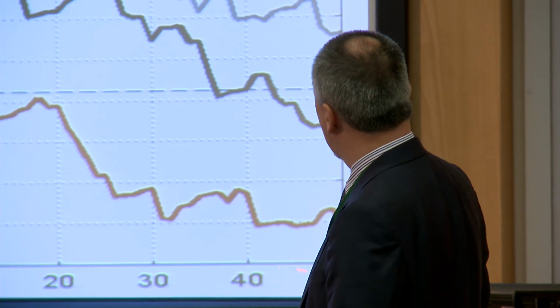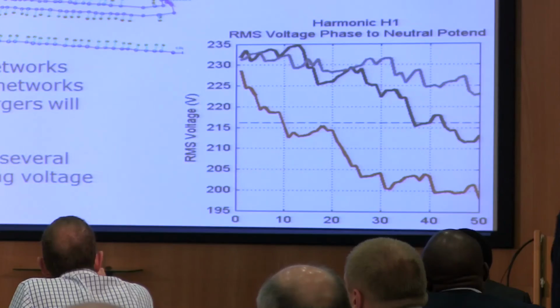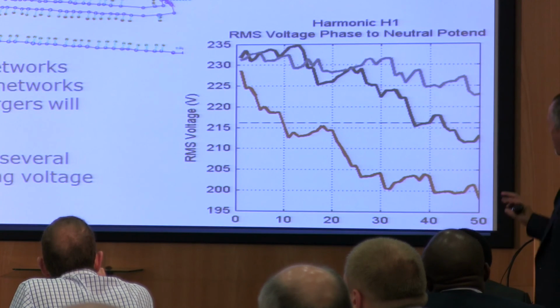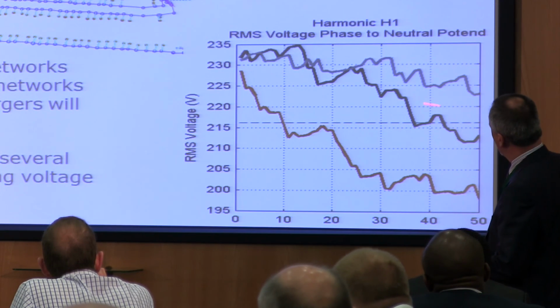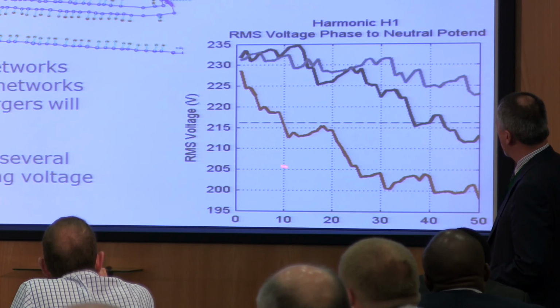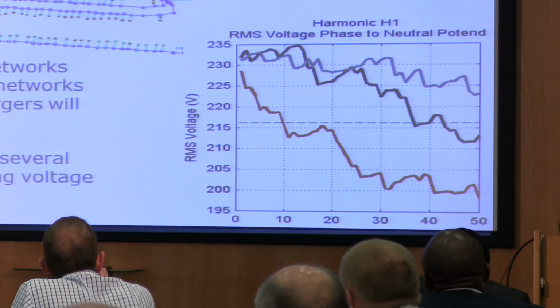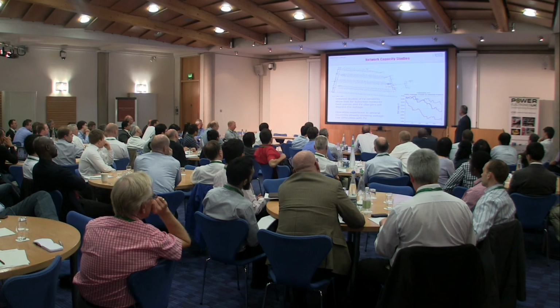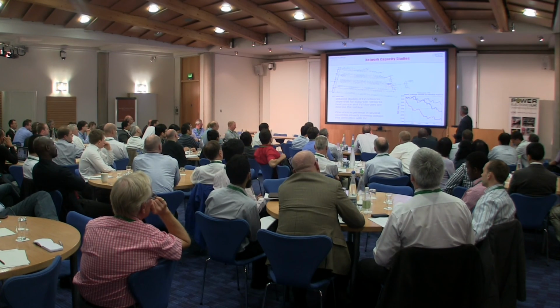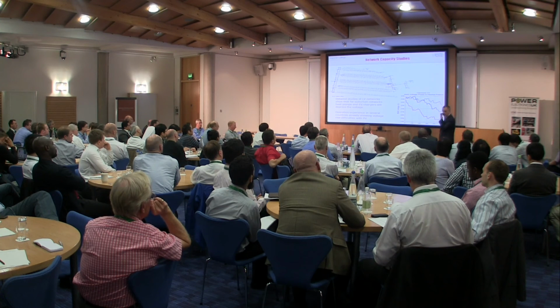50 houses on one of the particular feeders, and we put heat pumps on them in random allocations, then plotted the magnitudes of the three phase voltages. You see one of the phase voltages here dropping beneath the lower limit for a 230 volt network surprisingly early, after only 10 houses on the feeder were equipped with heat pumps.